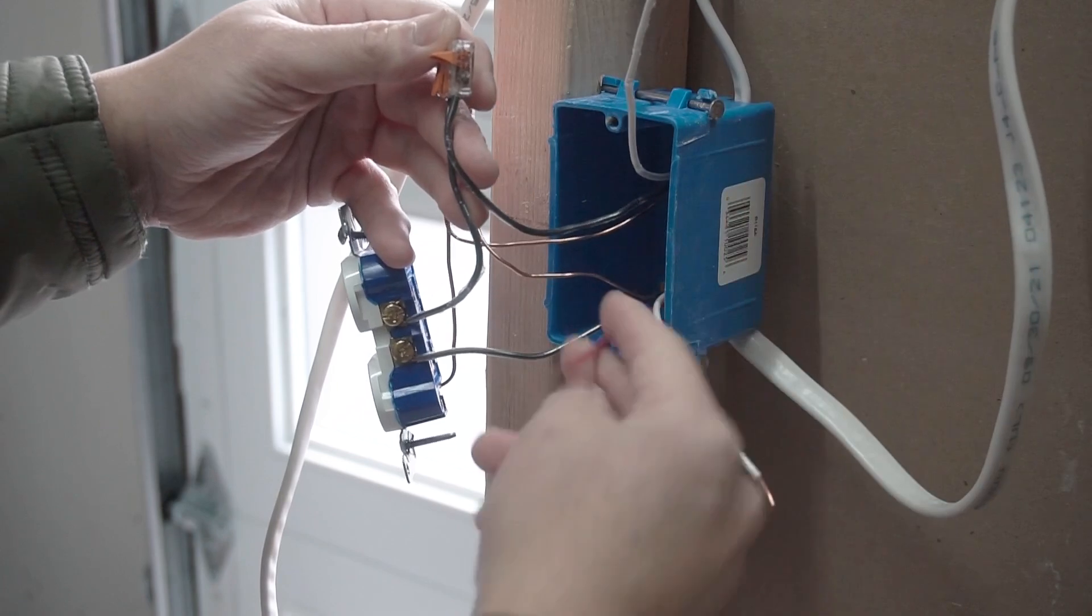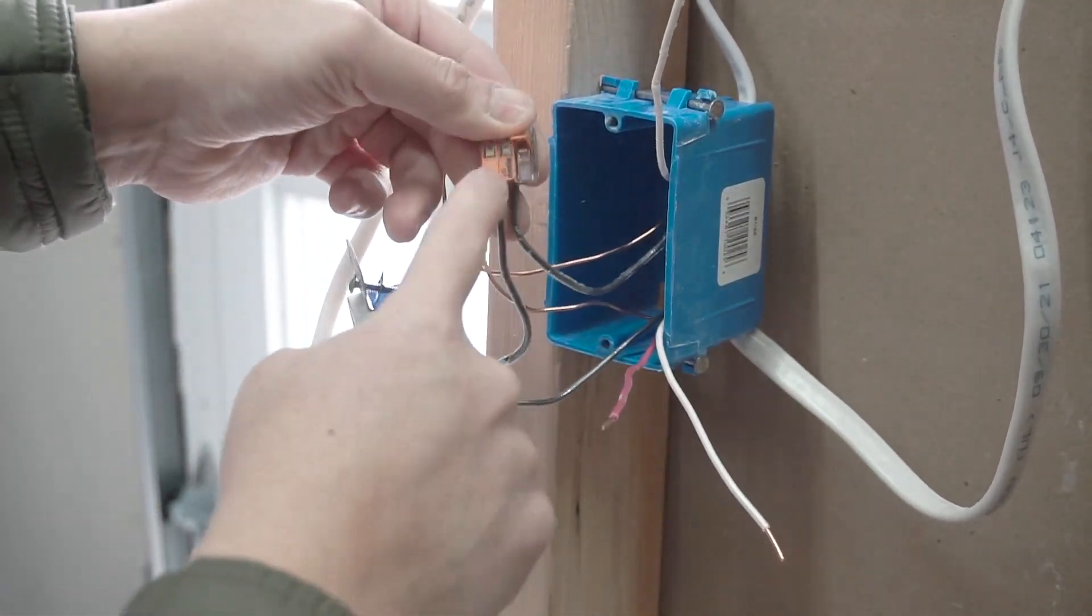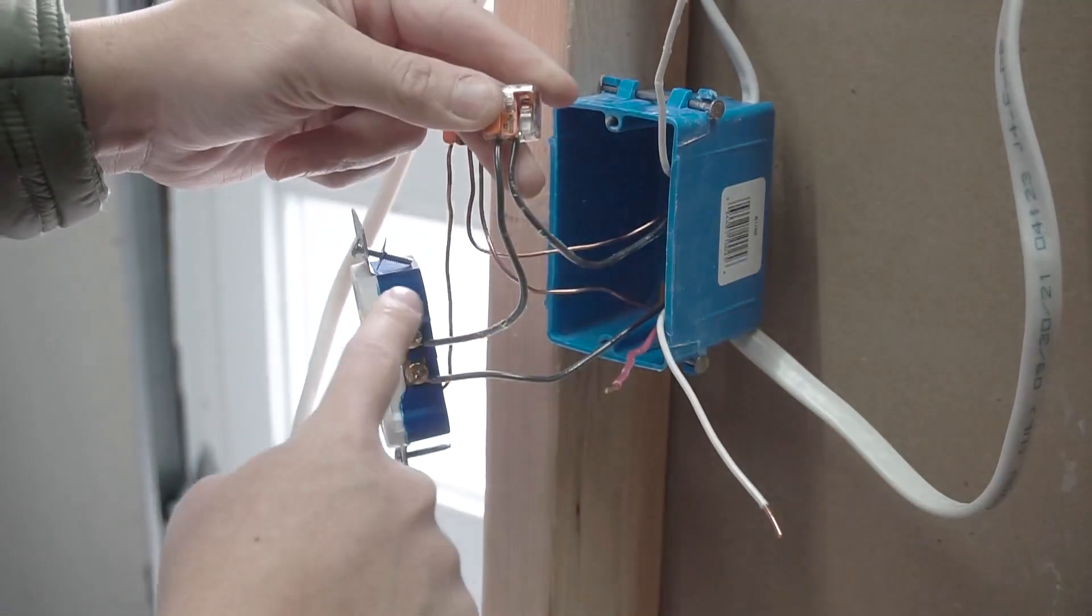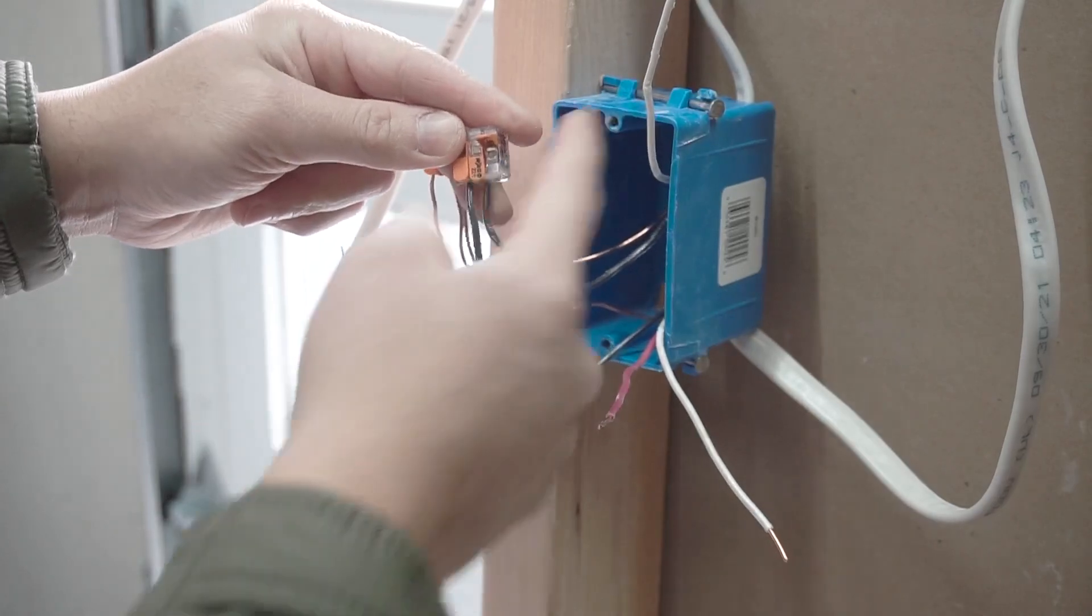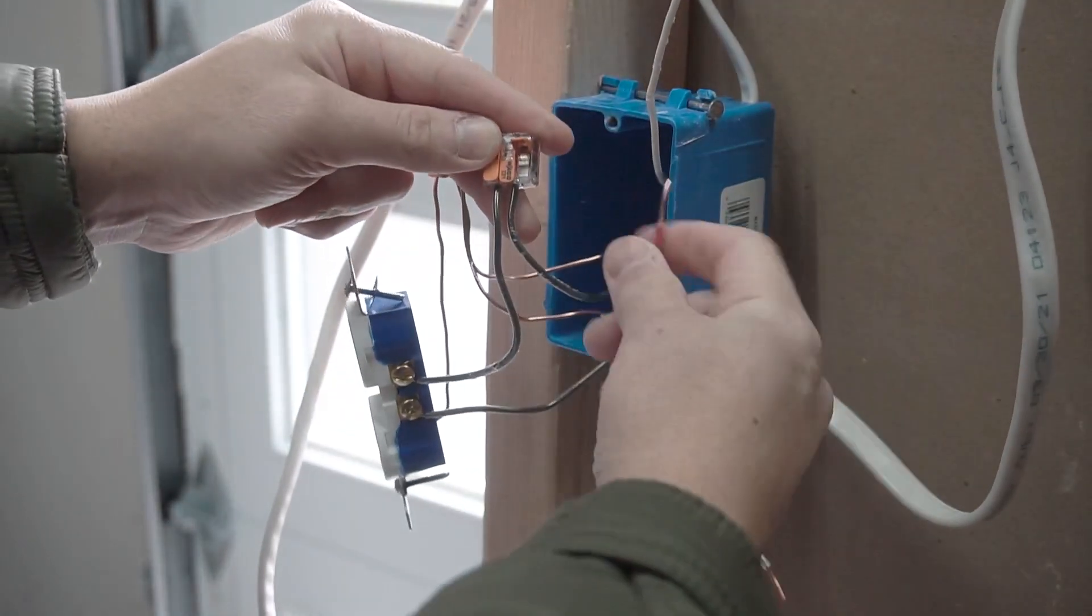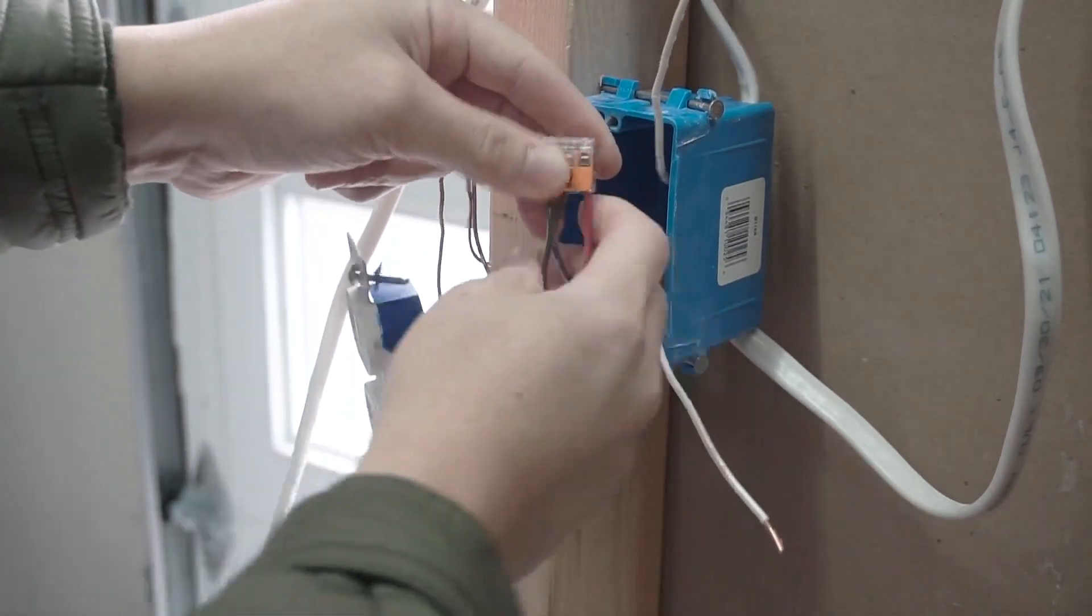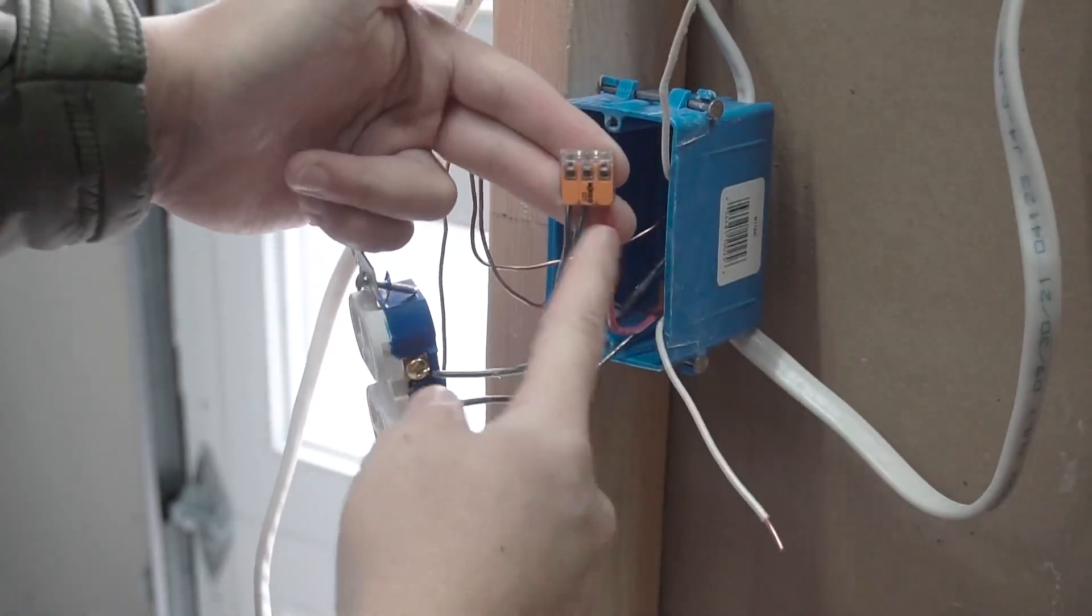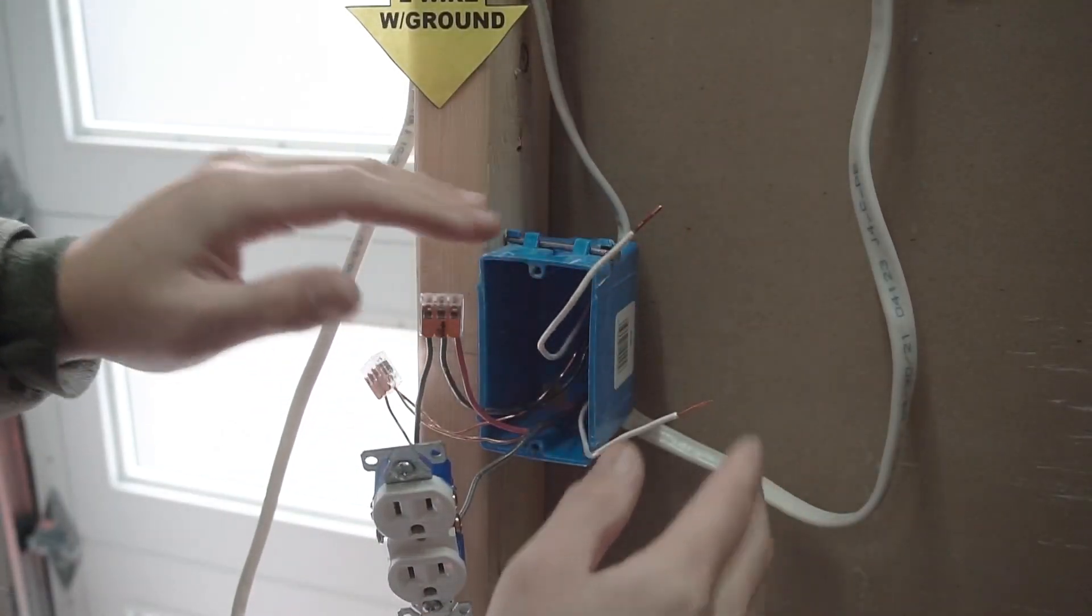Don't get weirded on this. We're going to take the red from the 14-3 and we're going to feed it with the hot wires on the Wago connectors. Now this is from the pigtail from the outlet, the hot from the 14-2 power source, and we're going to put this 14-3 red in there with it. So now you have two blacks, one red onto this wire connector.